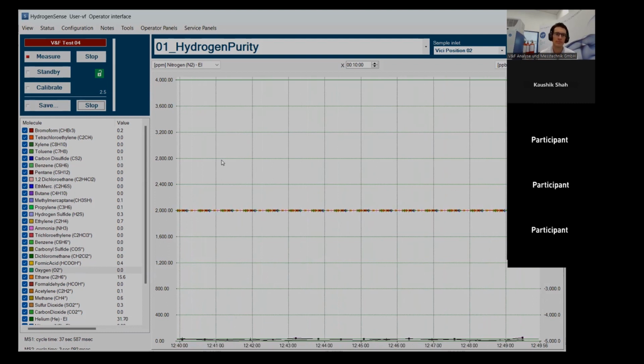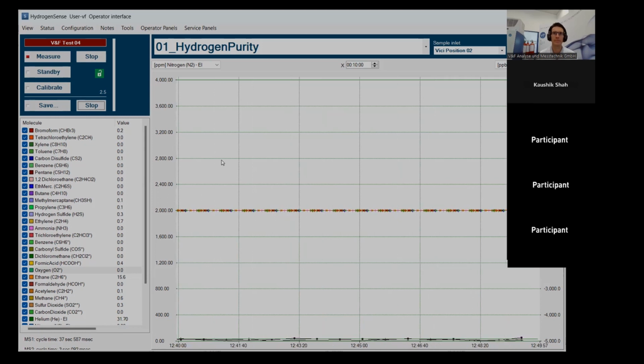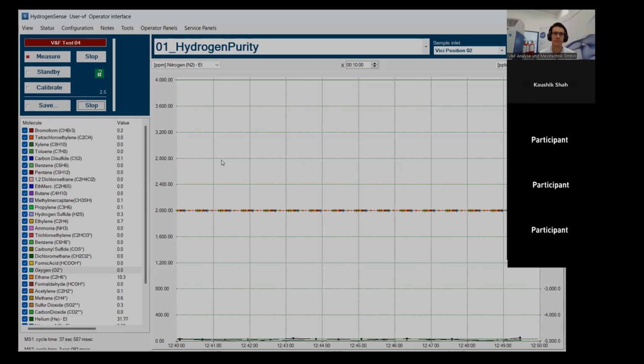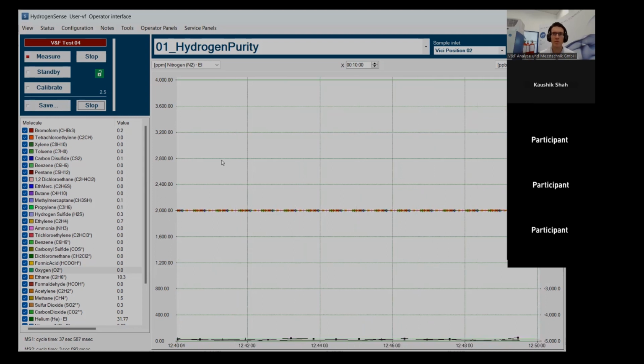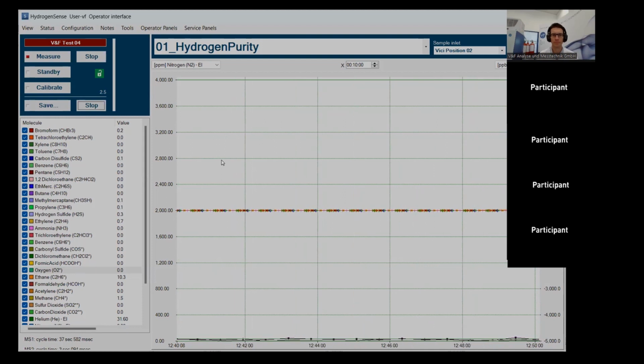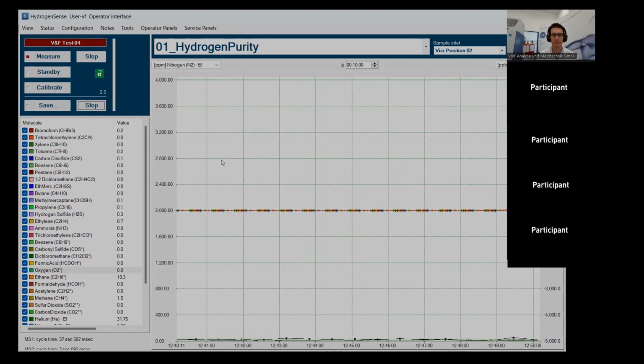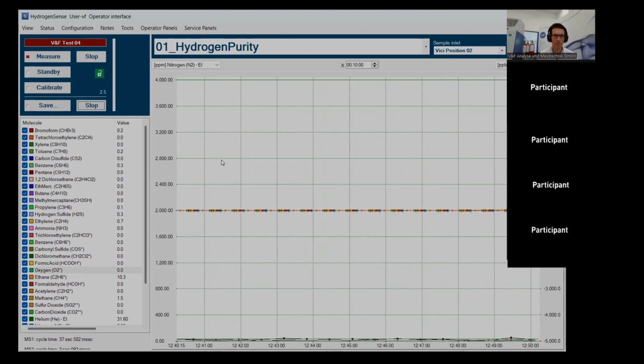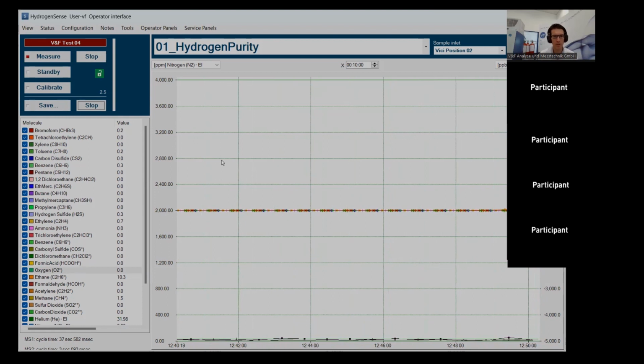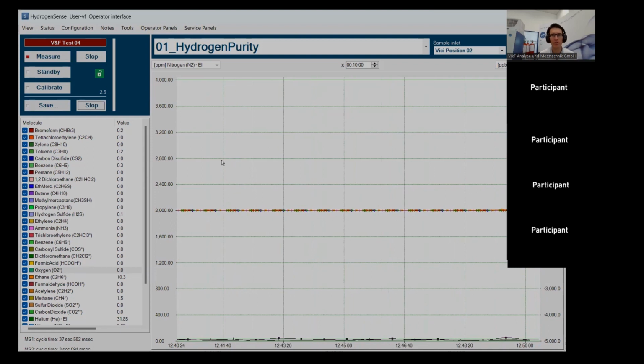Okay. It means that the user is purchasing calibration gases from your recommended suppliers. Yes. So overall responsibility will be yours to give the precise calibration and ensure that results are valid. Exactly. We have a list of calibration gases which suits our instrument and which also suits the production of the calibration gas.